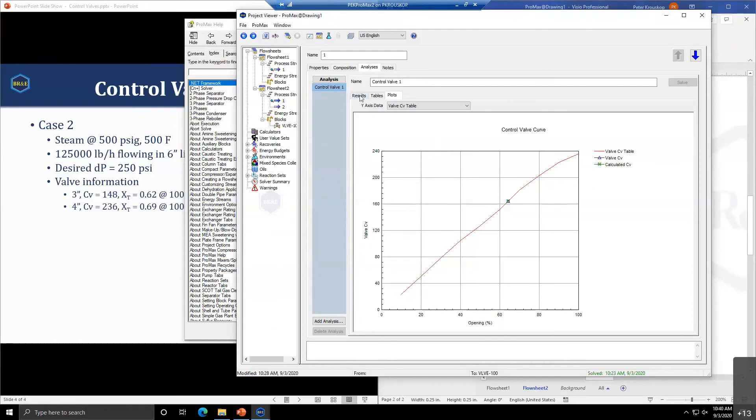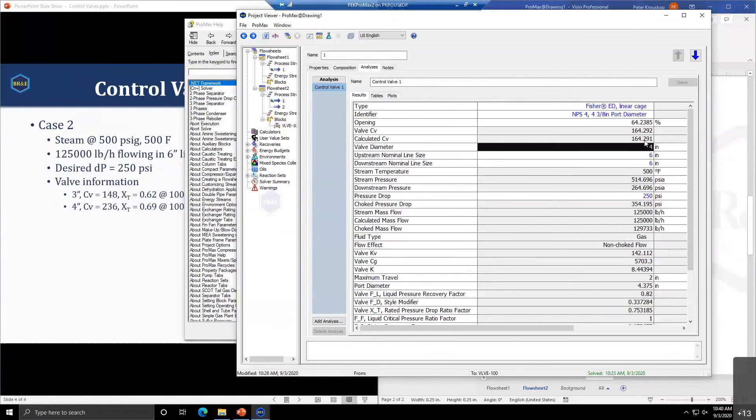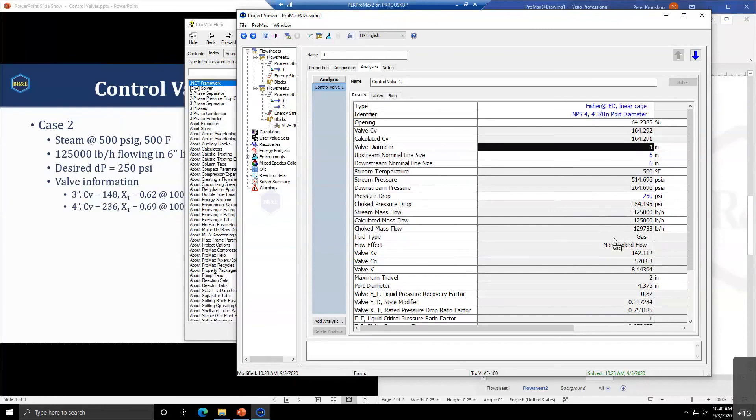As far as the results are concerned, it'll paint things yellow because it will state it's a choked condition. But the calculations are still applicable depending on your situation. The standards don't fall apart under choke conditions. We just paint things yellow so it becomes obvious these are under limiting conditions.